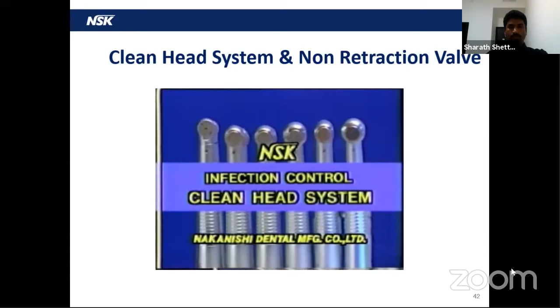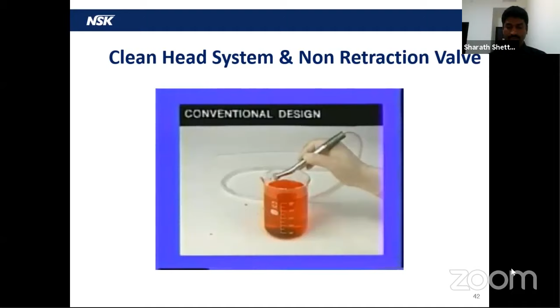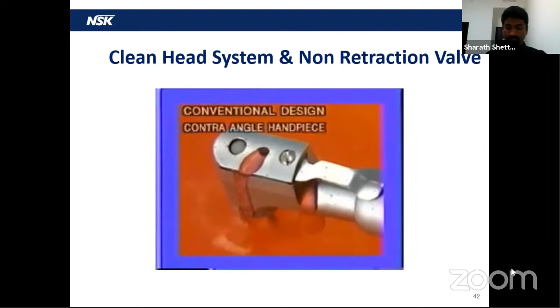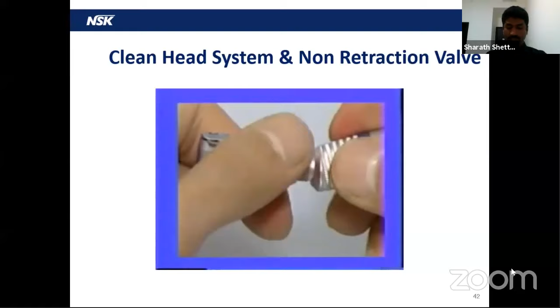Dental handpieces used in a patient's mouth tend to draw saliva, blood, tooth fragments, and metal chips from the patient's mouth into the handpieces. Sprayed water tends to be drawn back into the water line when the handpiece is stopped. A suction force is generated in the head when the air turbine handpiece is stopped. Gear-driven contra angles and handpieces also generate a suction force and draw foreign matters into the heads. Chances are that infectious virus may be drawn with these foreign matters into the headpiece. Those that were drawn into the water line may come back into the next patient's mouth.